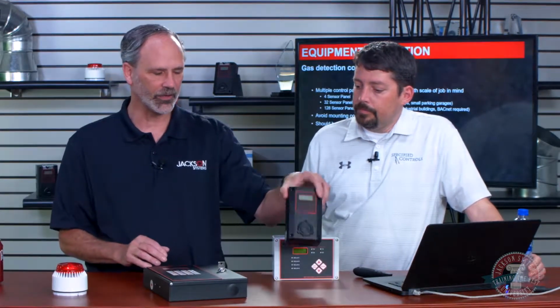So if a customer wants to tie all the sensors directly into his BACnet control system and then he controls all the fans, our personal opinion is that's a bad choice because now he's taking all the responsibility on him. We don't do that here. We have the capability to, but we always run everything through a control panel for liability reasons. All the fail safes are built in. So you can do directly to a building automation system. You can do proprietary protocol between a sensor and a panel, and then you can take the panel information and send it up to the building automation system.